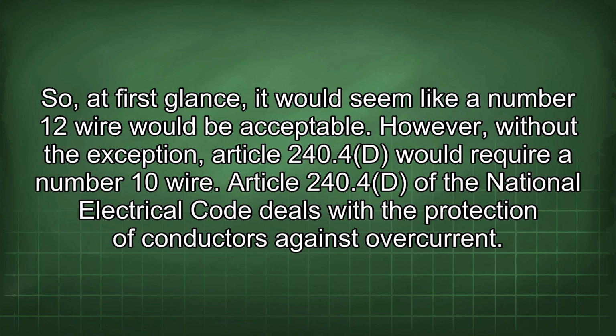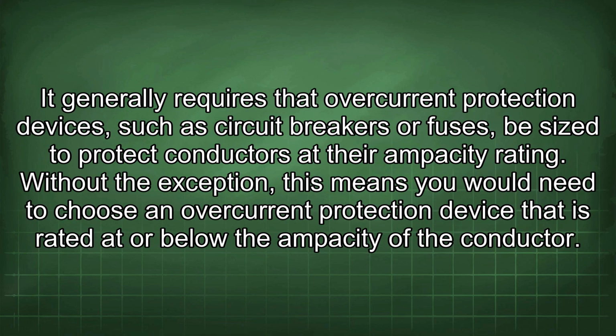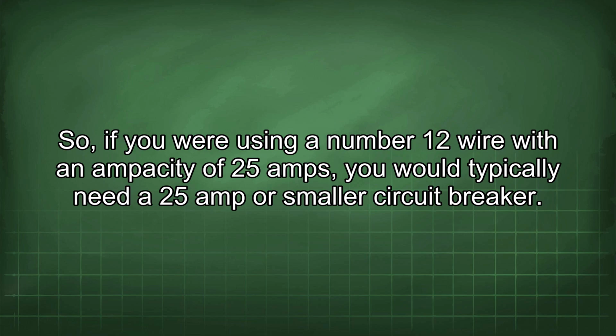Article 240.4d of the National Electrical Code deals with the protection of conductors against overcurrent. It generally requires that overcurrent protection devices, such as circuit breakers or fuses, be sized to protect conductors at their ampacity rating. Without the exception, this means you would need to choose an overcurrent protection device that is rated at or below the ampacity of the conductor. So, if you were using a number 12 wire with an ampacity of 25 amps, you would typically need a 25 amp or smaller circuit breaker.